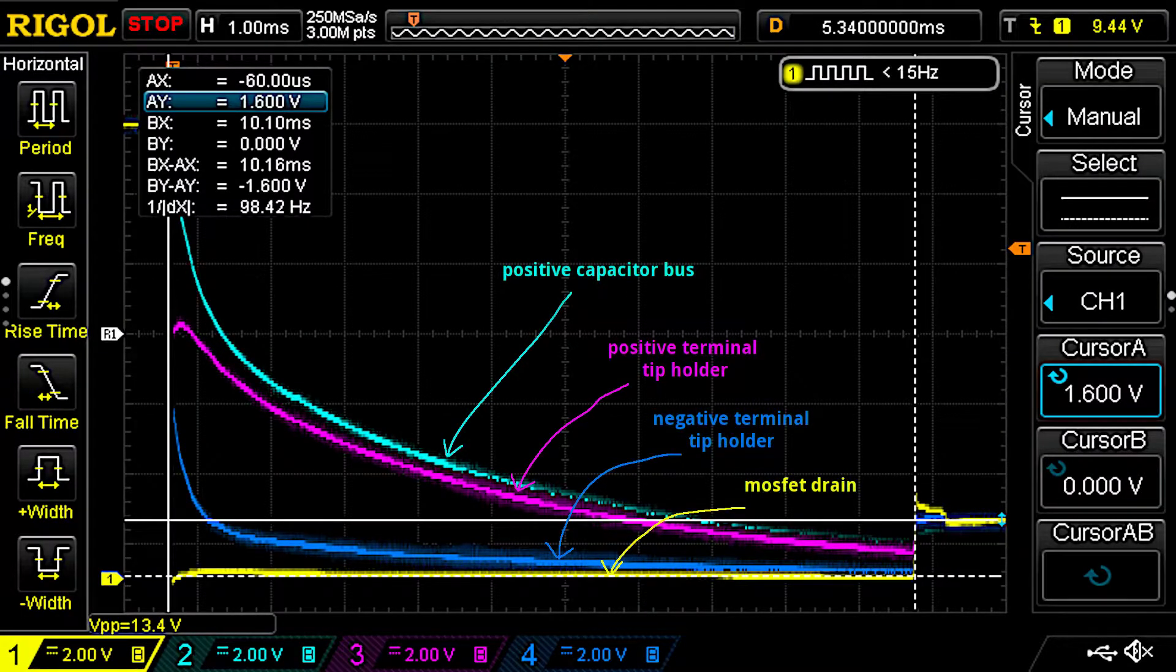This is the waveform showing the 13-volt 10-millisecond weld pulse. The difference between the green and red traces is 24 inches of 1-aught gauge copper wire with a resistance of about 0.2 milliohms.